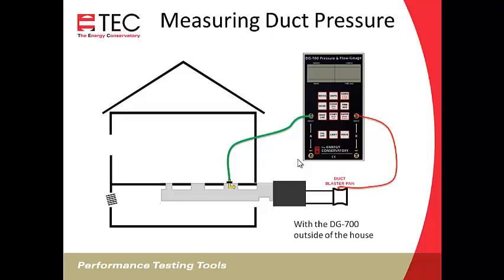Sometimes you'll run into situations where your DG700 is not in the house. Maybe you've got a package unit sitting out in the yard, and you're attaching your Duct Blaster fan right at the air handler cabinet. Maybe you're set up in a garage, or in an attic doing the test. If your DG700 is outside, then you need to reference the house. You need to run an additional tube to the house.